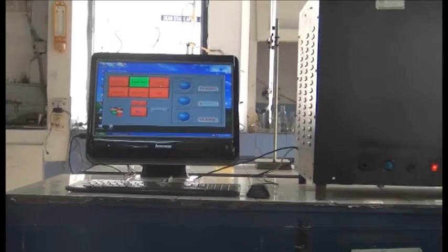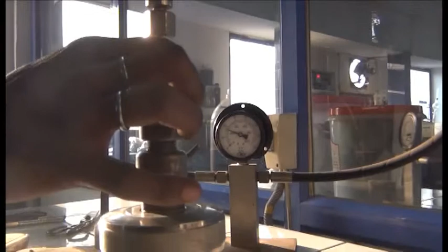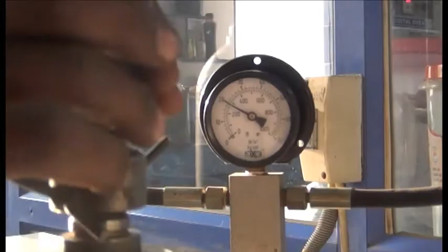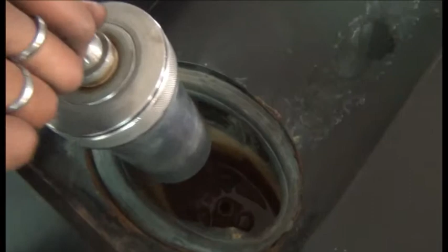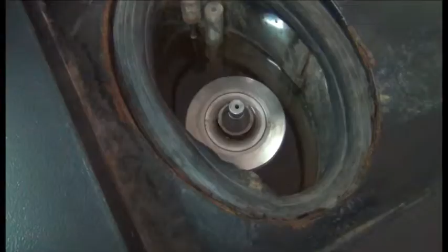acquisition system. The closed-loop operation with water handling system helps in fast operation. The instrument is equipped with USB communication ports for reporting of results. The instrument is capable of being interfaced with an analytical balance for automatic weight transfer and a printer. The instrument is a microprocessor-controlled isoperibol oxygen bomb calorimeter which is widely used for calorific tests. It is a compact, integrated, benchtop laboratory model designed as per national and international standards.